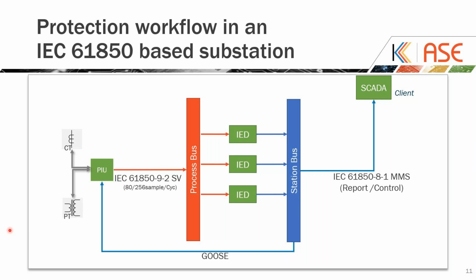And also we have the standard IEC 61850 client applications like the SCADA or the gateways that are connected to the station bus. But you can see that here there is a big difference from the previous workflow with the numerical relay: these IEDs are not physically connected to the CTs and PTs. Instead, we have a process bus concept, and this is something specific to the IEC 61850 substations.